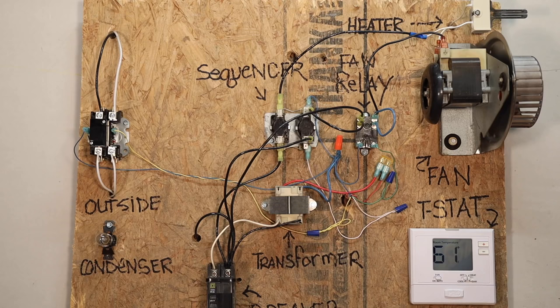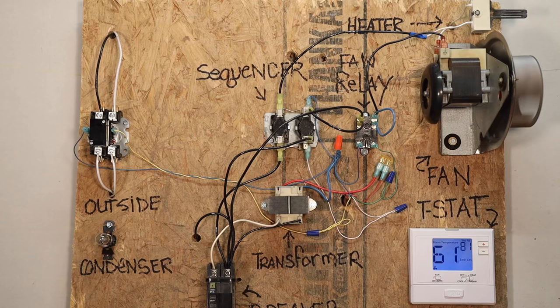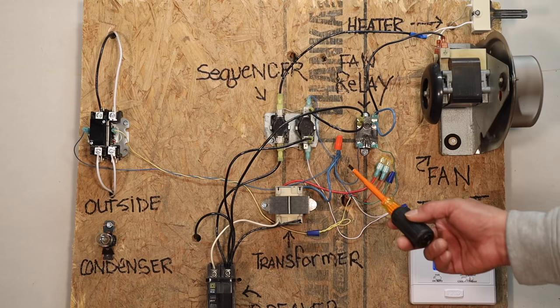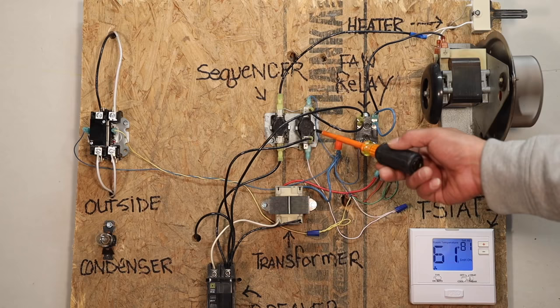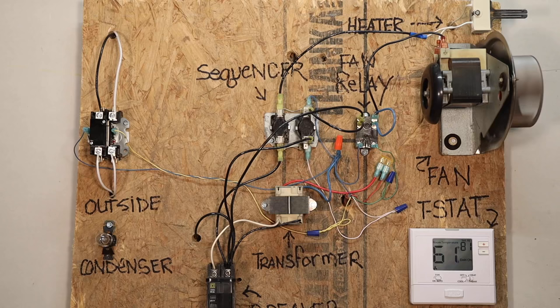So now let's put our thermostat over to heat. And like I was explaining before, the 24 volts is not going to the fan relay, but it's going to the sequencer, and your power is being passed through because it has made a circuit. It's going through the center part and it turned on your blower motor.